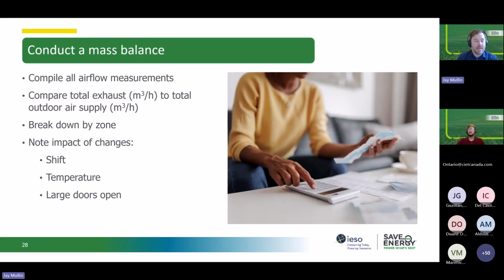That next step of conducting the mass balance is where you compile all your airflow measurements. So you want to be comparing that total exhaust to total outdoor air supply. You want to break it down by zone within the facility, as mentioned before, but also you want to note the impact of changes in operations. So different shifts, different temperatures, seasons outdoors, when loading bay doors are open versus when they're closed, because those can all impact airflow. They can all impact pressurization within the facility.